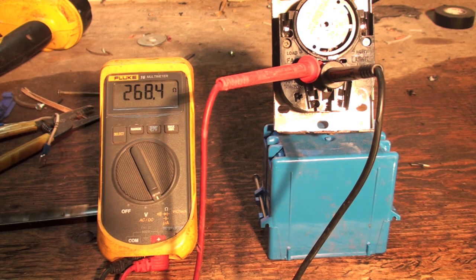Which is a very small heater, but I do show continuity through it, so I know the heater is there and is good. So the heater is going to turn the fan on a little bit early, and then when the cold air that's in the return kind of shocks this thing as it comes back - the return air is going to be cold.